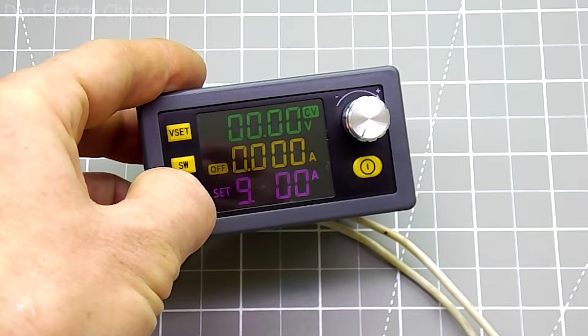This will result in the short-circuit current being displayed on both the converter and the multimeter. When I short-circuit the wires, compare the readings on both devices. The current is now limited to 100 milliamps. I short-circuit the wires and see what happens. For the first few seconds, the multimeter shows a lower current, not 100 milliamps, but about 60, then it recovers to the set value.